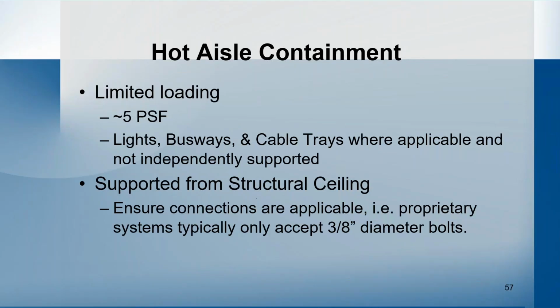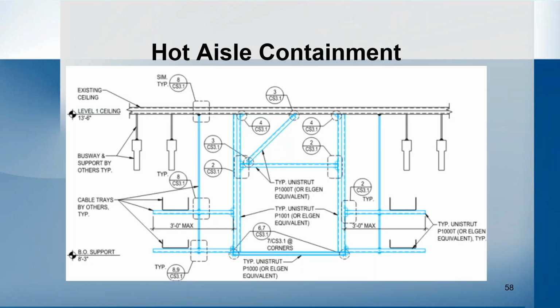With your hot aisle containment, typically it's some limited loading, typically 5 PSF. There may be some light busway and cable tray support required as well. So some additional limited support, but typically the loading is relatively light. And these are typically supported directly from that structural ceiling that I showed you some pictures of earlier in the presentation. So you need to ensure your connections are applicable to proprietary systems. Most of the proprietary ceiling systems only accept 3/8-inch diameter bolts, so that's just something to consider when installing and designing them. And this is what the typical hot aisle containment would look like.